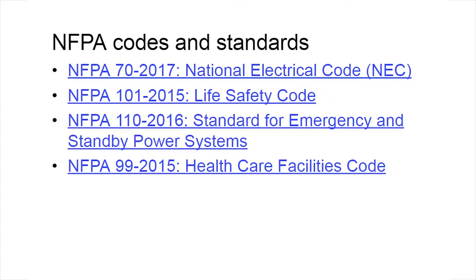The National Electrical Code provides a lot of detail about the installation requirements for standby systems. The Life Safety Code covers performance requirements. NFPA 110 covers the installation requirements for standby power systems, including sources, some of the distribution and transfer switches. It's worth noting that NFPA 110 covers only installations whose failure could adversely affect the safety of human beings. It excludes other kinds of systems. And NFPA 99 covers installation and performance requirements specifically for standby systems in healthcare facilities. I'll look at those codes with a primary focus on the NEC.